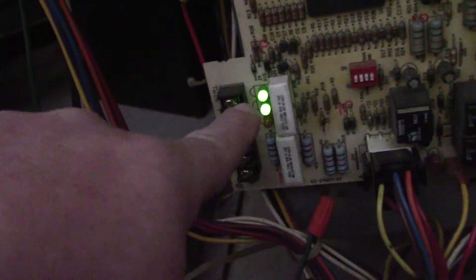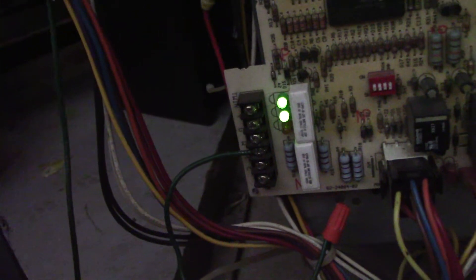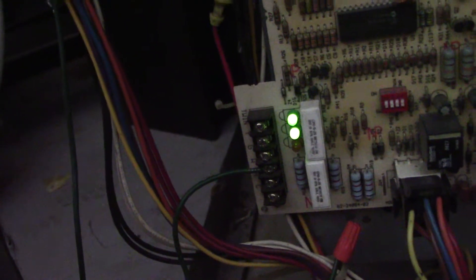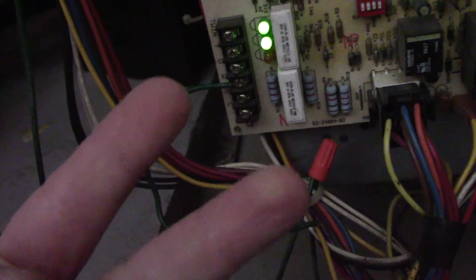For troubleshooting, right here I know I got power and the transformer is good, life is great. But if you walk up, you do not see the lights on right here, that's going to tell you one of two things. No 24 volts, bad board.